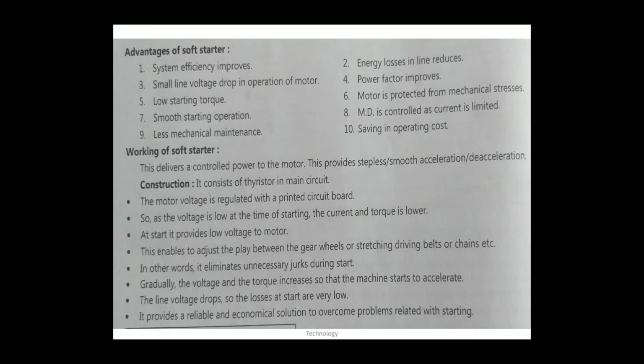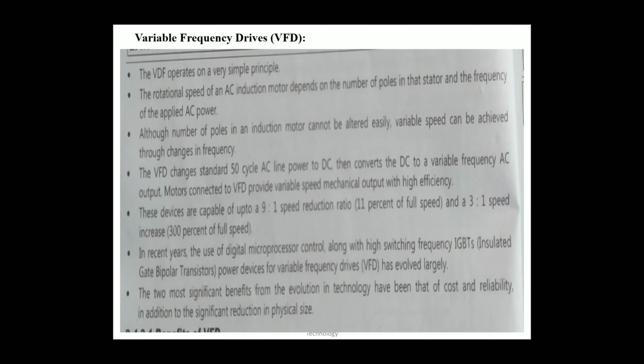Means, in a soft starter we use a power electronic device, that is the thyristor, to control the starting current of the motor. The next one is the variable frequency drive, that is VFD. VFD operates on a very simple principle. The rotational speed of an AC induction motor depends on the number of poles in the stator and the frequency of the applied AC power.